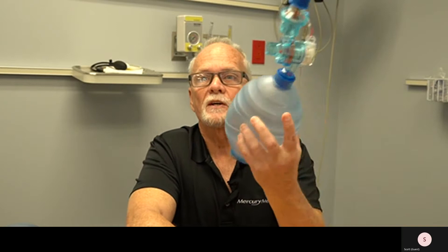This is the average adult bag — it's about a 1,500 cc bag. I tried to figure out where that size came from. Why is it 1,500 cc? I even looked at the paperwork submitted for the original Ambu bag back in about 1956–1957, and even in their patent paperwork, there was nothing that identifies the size of the bag.